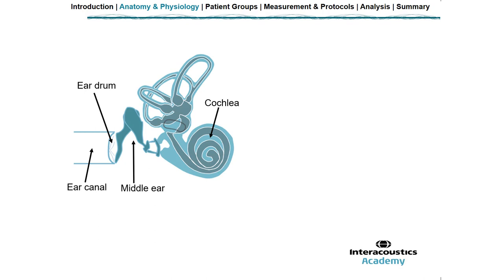Now let's look at some basic anatomy and physiology, and some OAE assumptions. Here is a diagram of the ear. We have the outer ear with the ear canal and the eardrum, the middle ear, and the cochlea. When we present a sound to the ear it travels through the ear canal, middle ear, and eventually reaches the cochlea — this is where the OAEs are generated. OAEs are the sounds generated by the movement of the outer hair cells in a healthy functioning cochlea in response to an external stimulus, and can vary from around minus 10 dB SPL to positive 30 dB SPL.